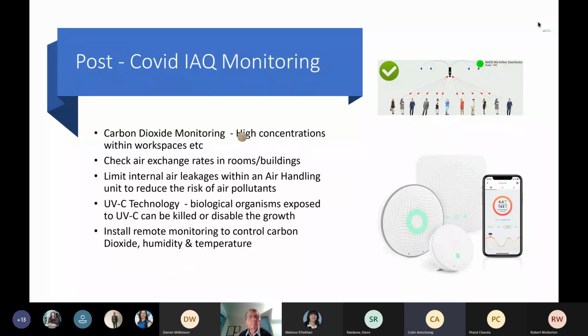While there are many possibilities to improve the ventilation solutions, I think it's important to recognise that there is current technology and knowledge that already allows the use of many rooms in buildings during COVID. We can still use these rooms as long as a risk assessment is conducted. Check that we've got the right air exchange rates. That's a massive one for me. As long as you're giving good advice, everything's working well, and you've worked out the air exchange, carry out that risk assessment. I think that's the first one.